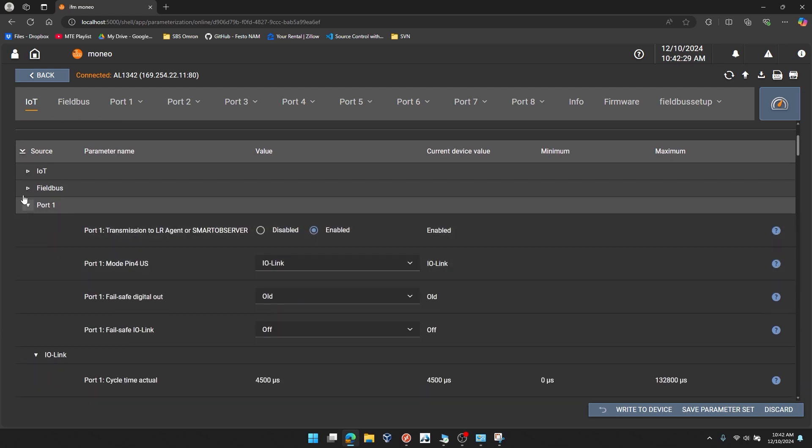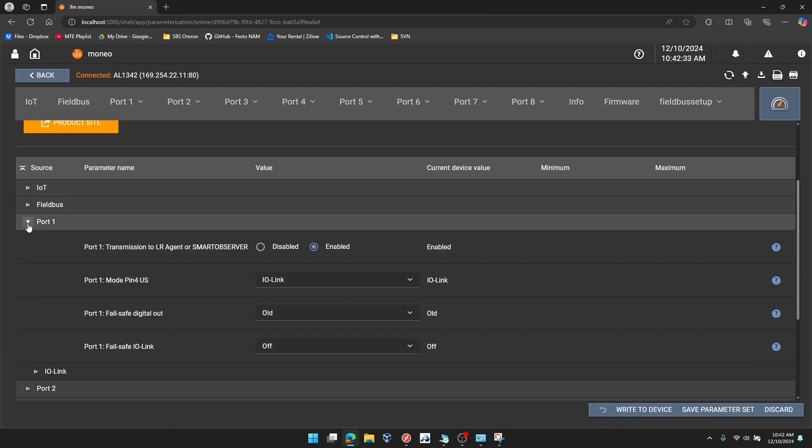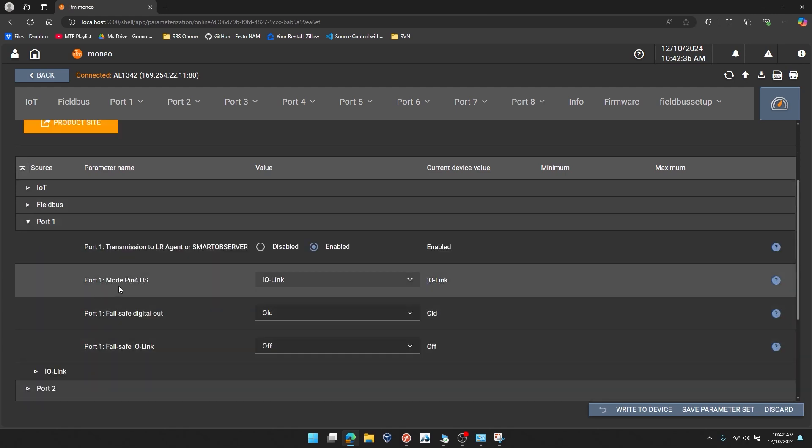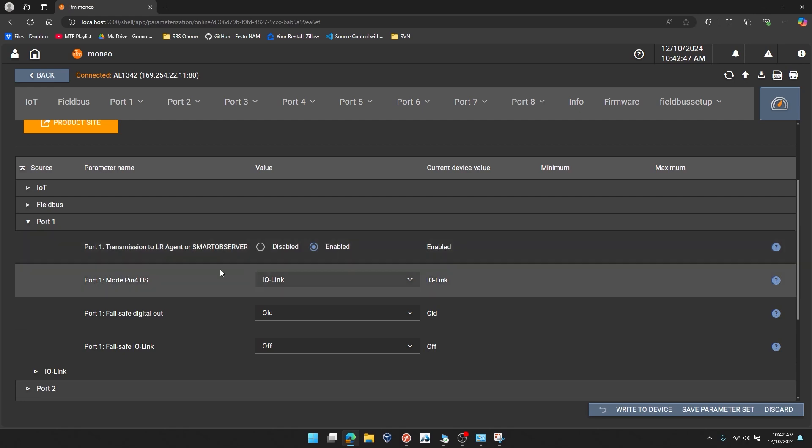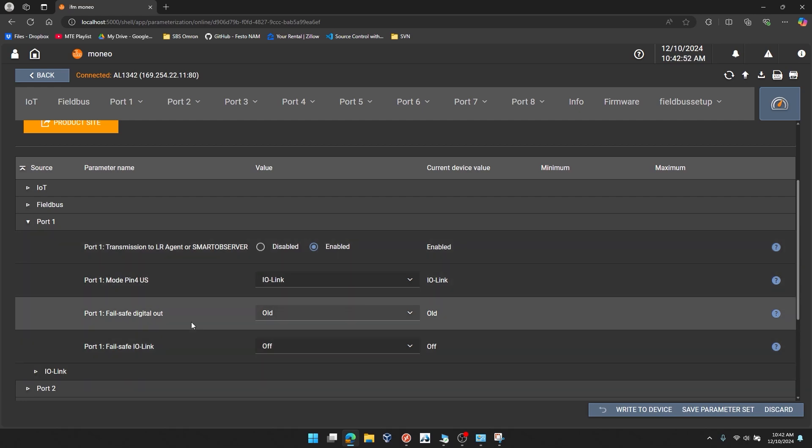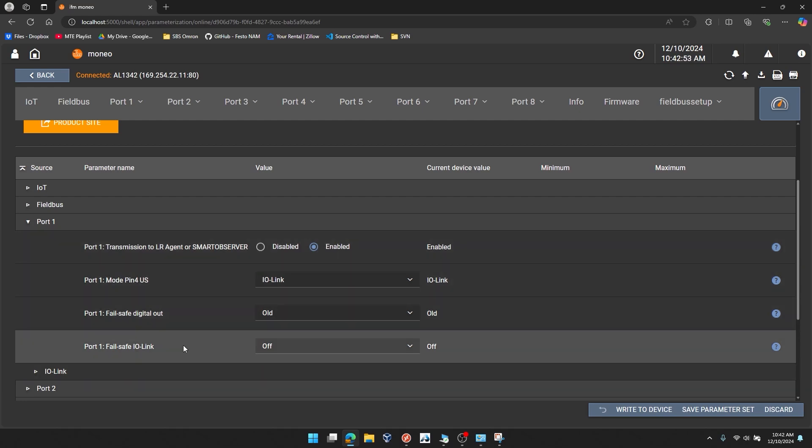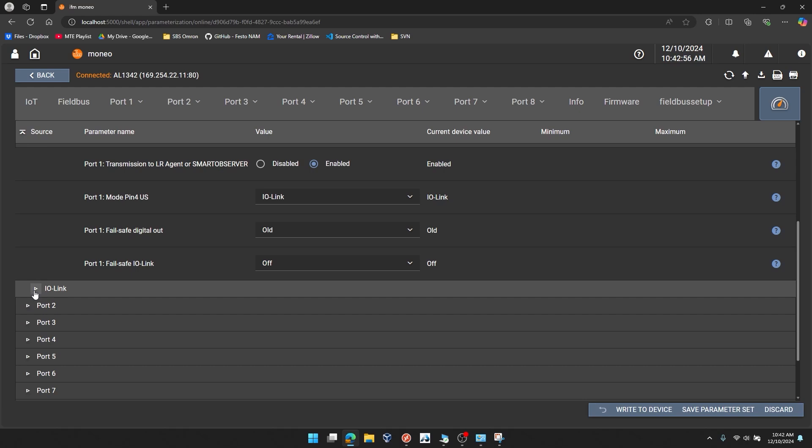I'll scroll down to port 1. If you want to get down to that quickly, you can click a little caret here next to source. I'll expand port 1. And you can see the default setting for the pin 4 mode is already IO-Link. So that's great. We don't need to change that. The transmission to LR agent or smart observers are enabled. We don't need to change that. Or either of the fail-safe settings. You can leave this as old and this as off.